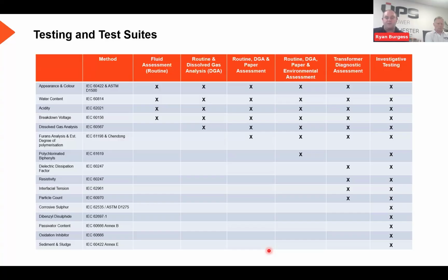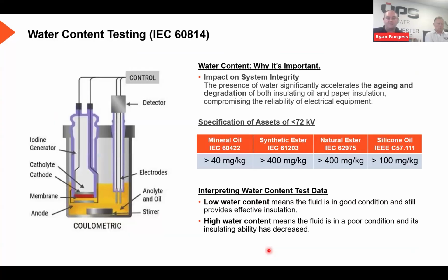You can then monitor it better through those complementary tests. And then finally, you've got investigative tests. These are predominantly used to provide compliance to environmental specifications or operational requirements. And today, all the testing that we're going to talk about would be covered under the routine DGA and paper assessment, which for the information it gives you is the minimal amount of information that you need to determine how the asset is operating and aging through the DGA and the paper assessment, and how the fluid itself is doing over time. And that's it on test suites.